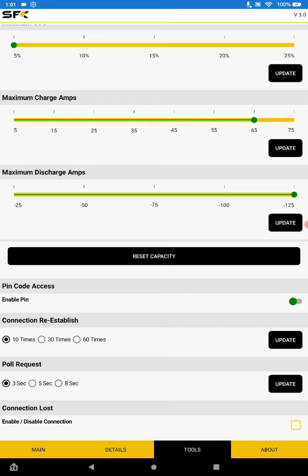That tells how many times we're contacting the BMS for updates. 3 seconds means every 3 seconds we confirm with the BMS what's going on. If you're having interference issues, you can up it to 5 or 8 seconds. The last setting is whether, if connection is lost, it will reattempt to establish connection with the device.